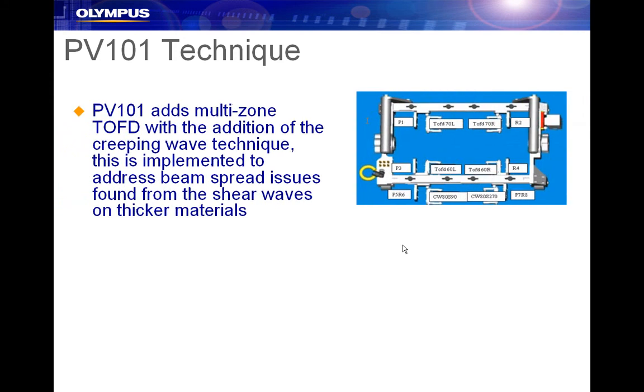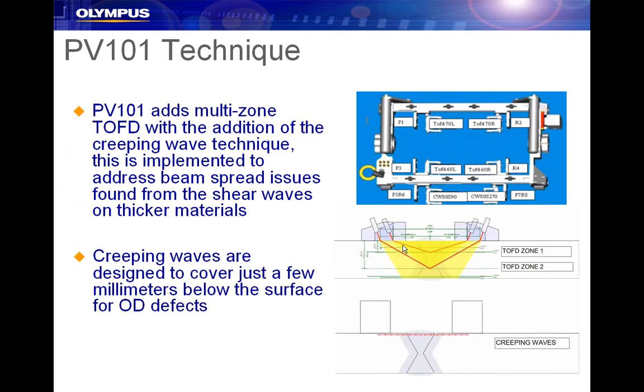As mentioned previously, as welds get thicker, we often use creeping waves to assist in code compliance and coverage. Here a scanner is shown utilizing TOFD at both the root and volume and a pair of creeping wave transducers covering the very top of the weld. The creeping wave transducers are designed and set up to cover only a few millimeters below the surface, where the first zone of TOFD will have a weakness. By refocusing the second pair of TOFD lower into the volume, we're able to get sufficient coverage and detection at the back wall area.